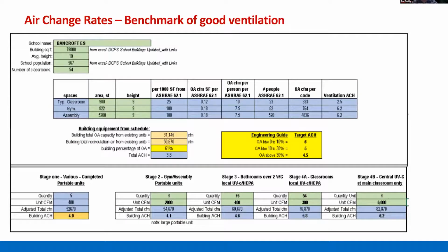What we've also created, this is just a typical school we've done as part of that, is we start looking at the air change rates. If you remember, originally we are trying to target that 6. The path that most of the clients have started to go quickly is buying these portable units. We are then looking at different stages of either running an assembly area or gym units in full 100% fresh air to drive that ventilation into the rest of the spaces. We do have to be wary of transfer air and still meet code. But with some of the conference rooms, some of the auditoriums, assembly spaces, that's our best mode of getting fresh air into the space.